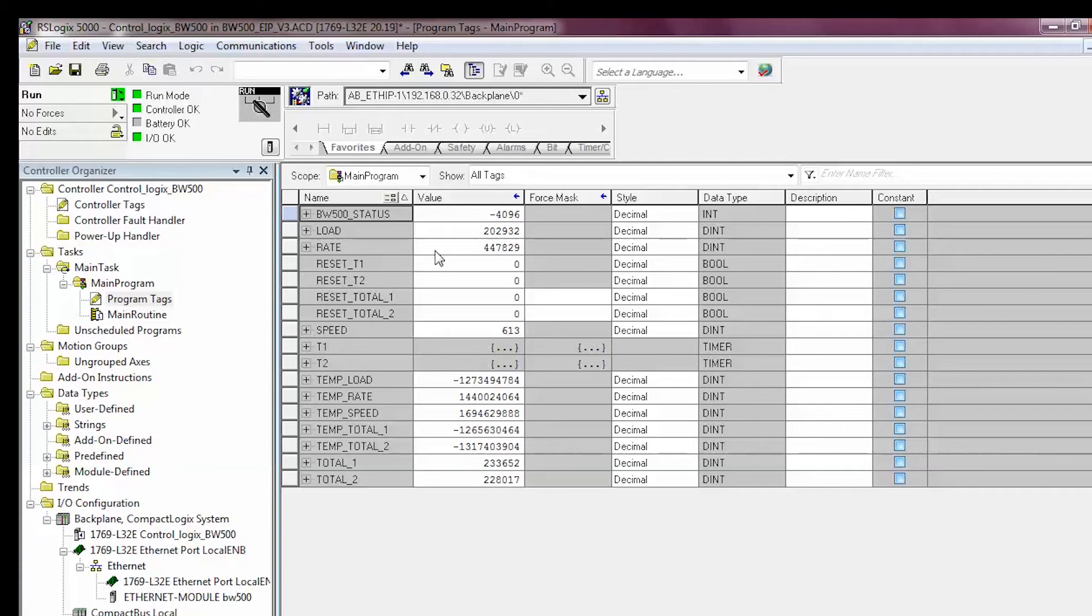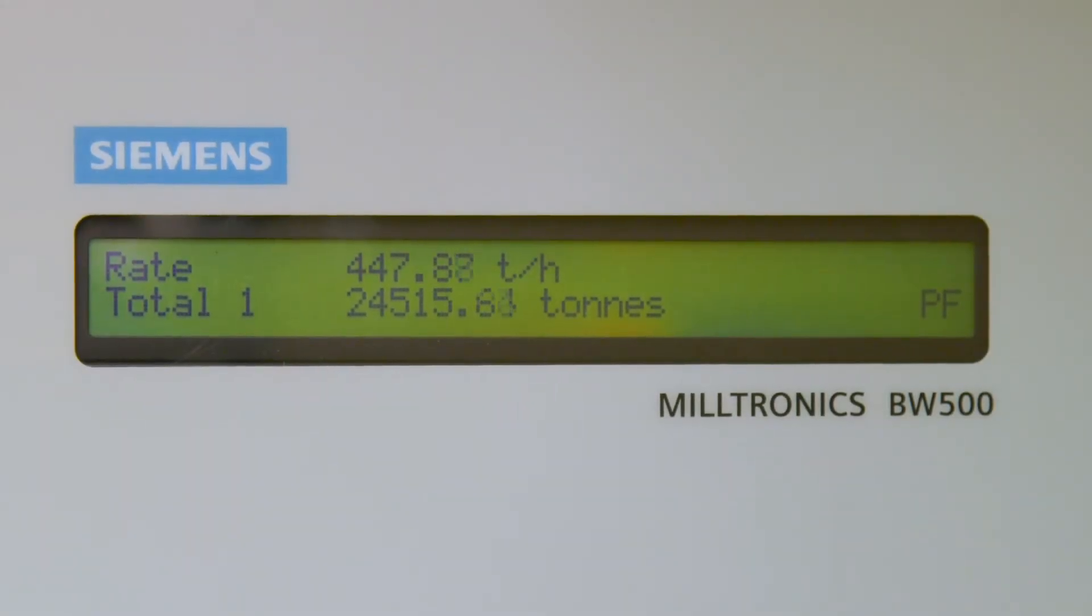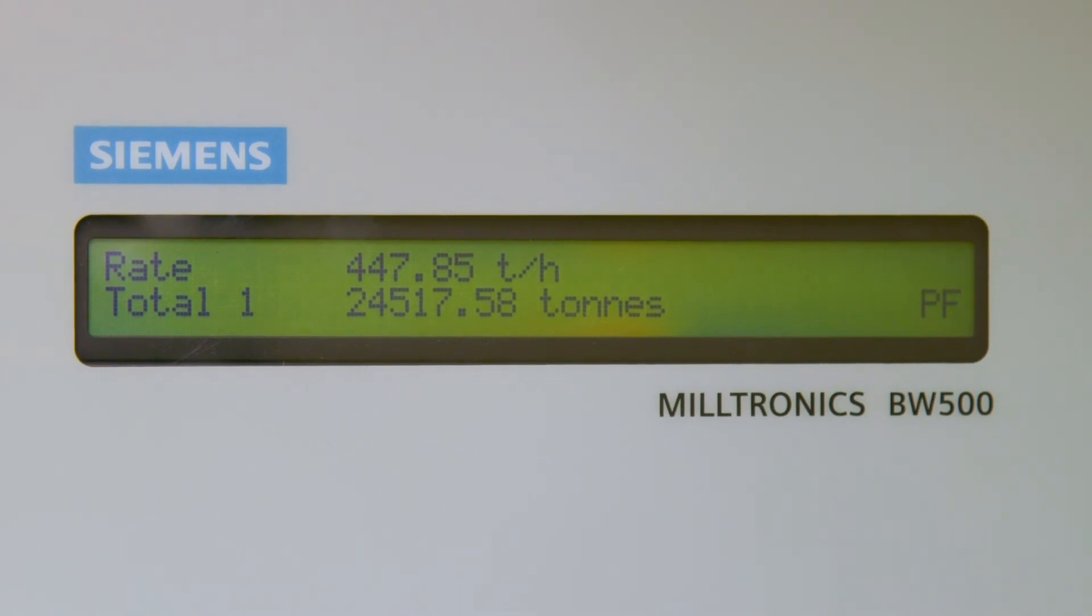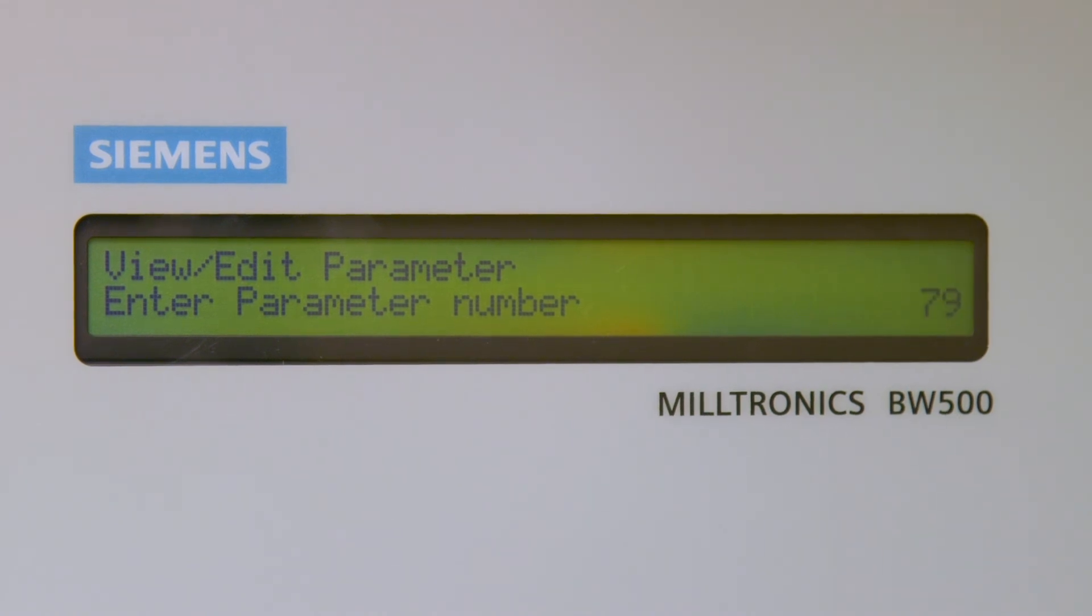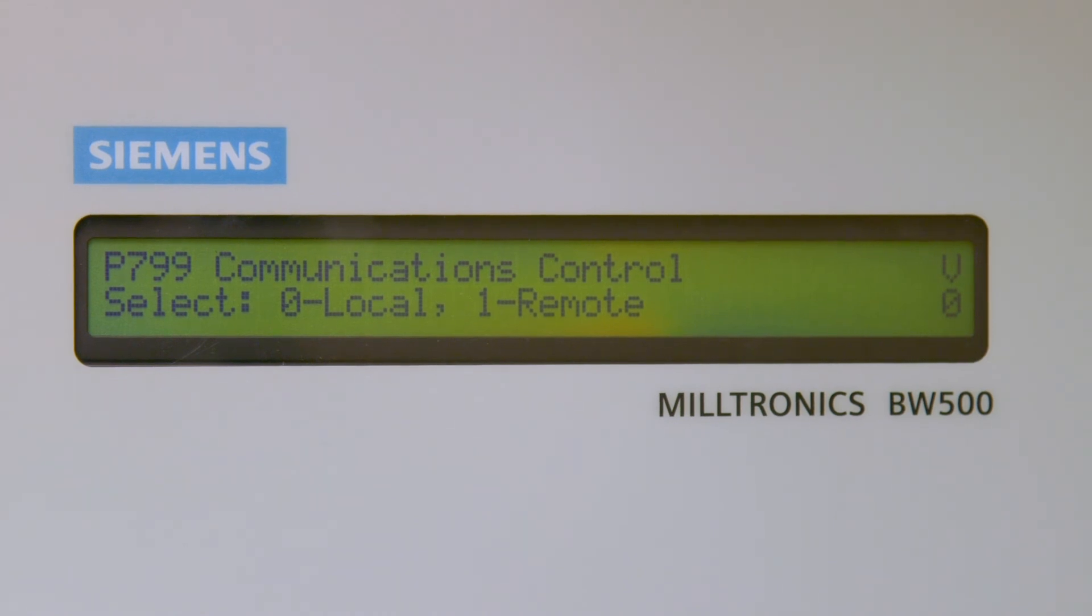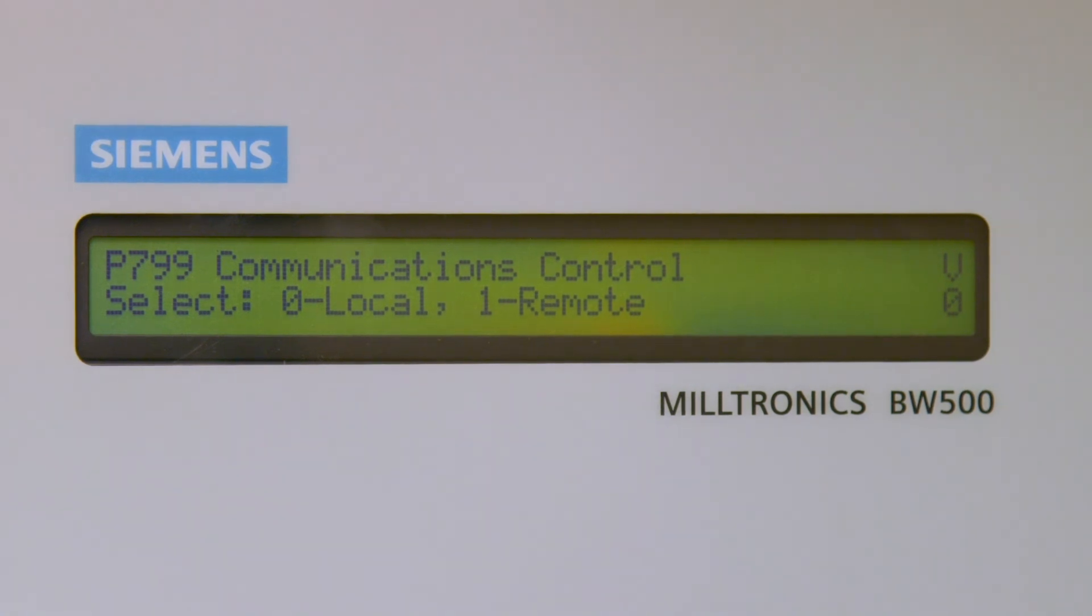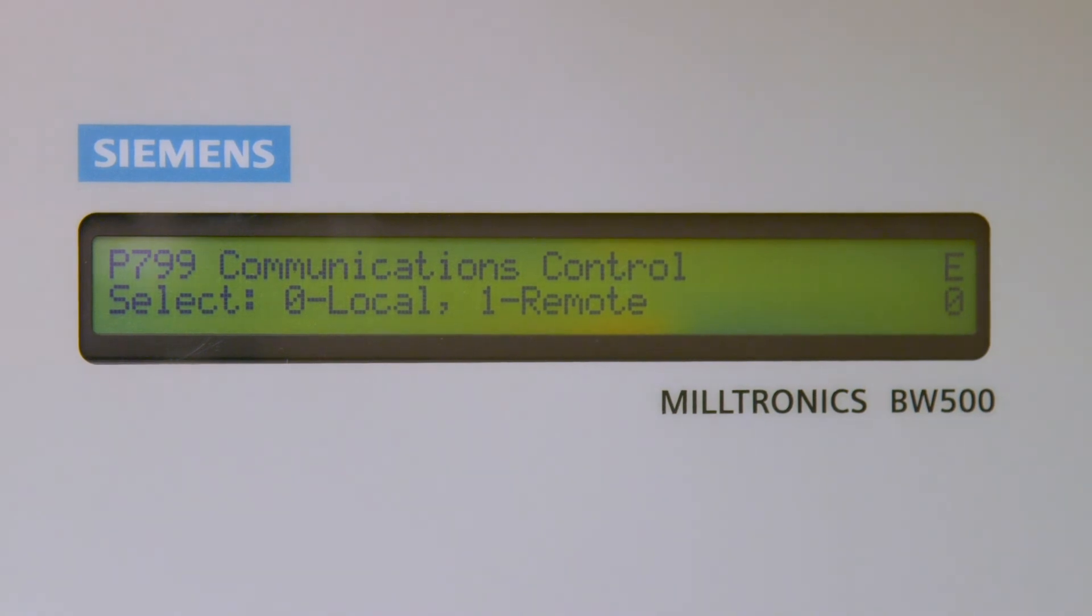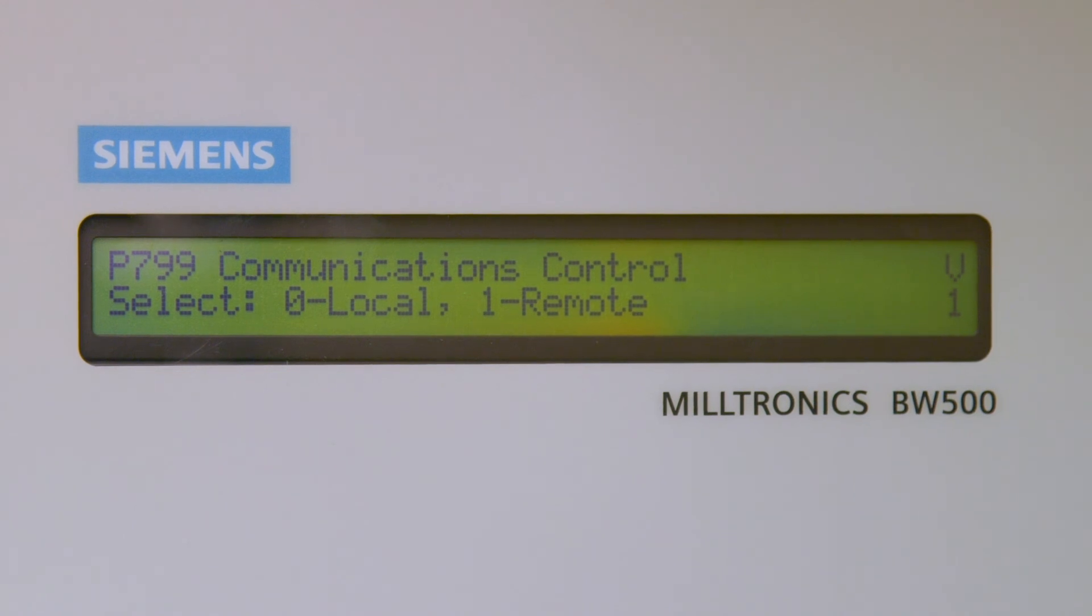Many processes will require the BW500 totalizers to be reset via communications. Ensure P799 on the BW500 is set to 1 for remote communications enabled. You can do this by pushing the PAR button on the BW500 two times until the display shows View/Edit parameter. Enter 799 from the keypad of the BW500 and push the Enter key. If the value of P799 does not equal 1 for remote, then push the Enter key on the BW500 keypad to change the character on the display in the top right-hand corner from a V to an E. Enter 1, then push the Enter key. Push the Run key to put the BW500 back in the Run mode.